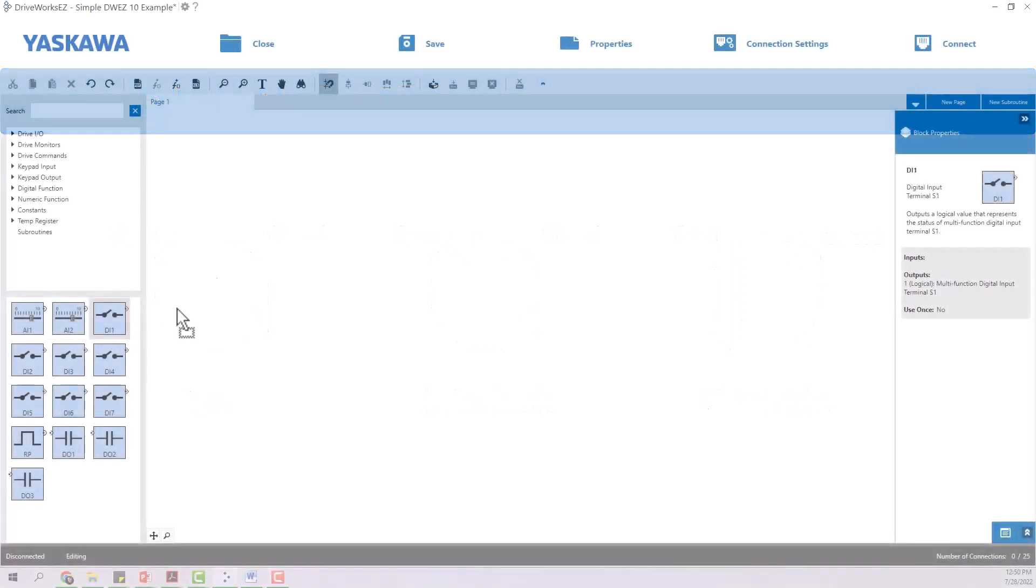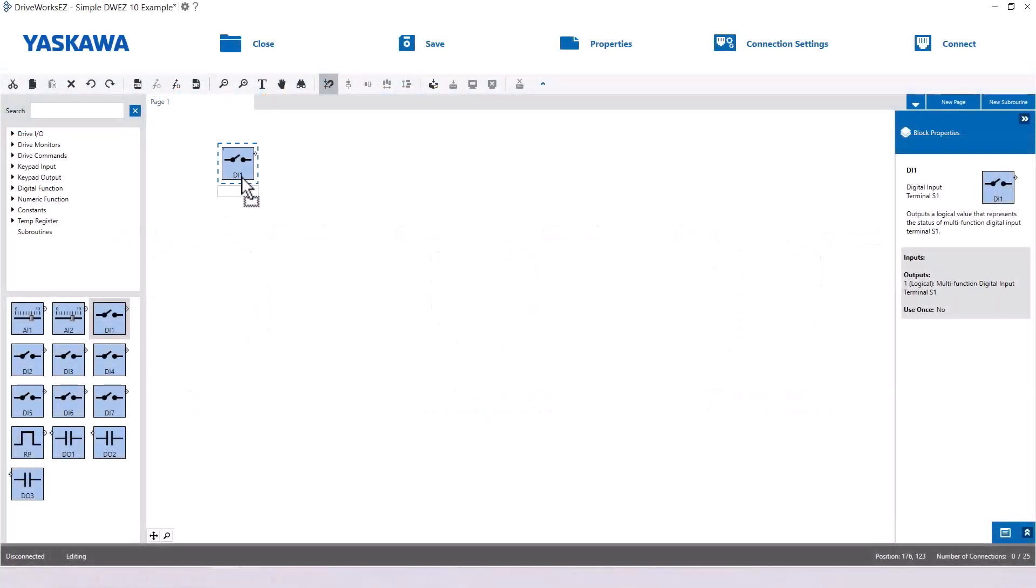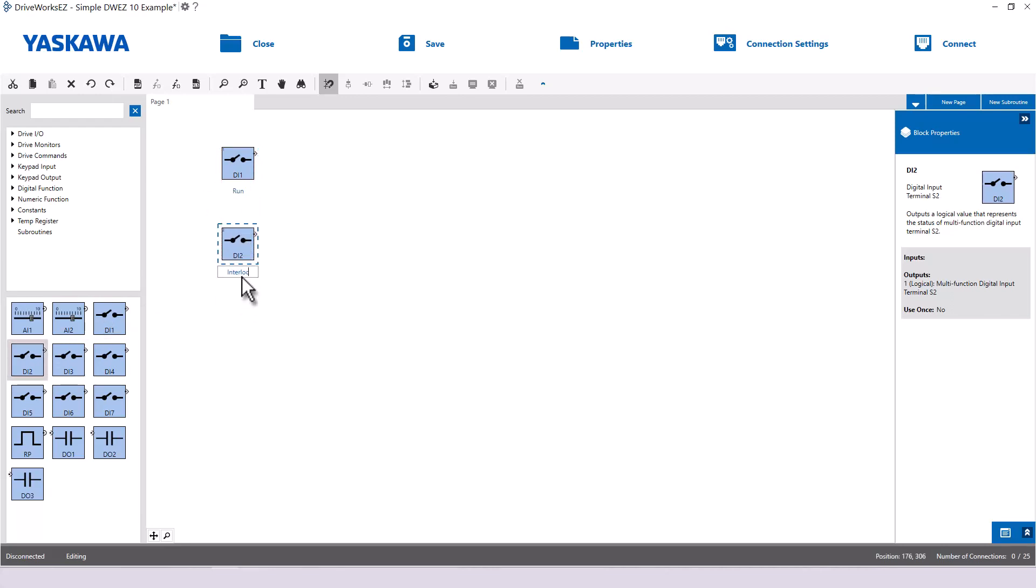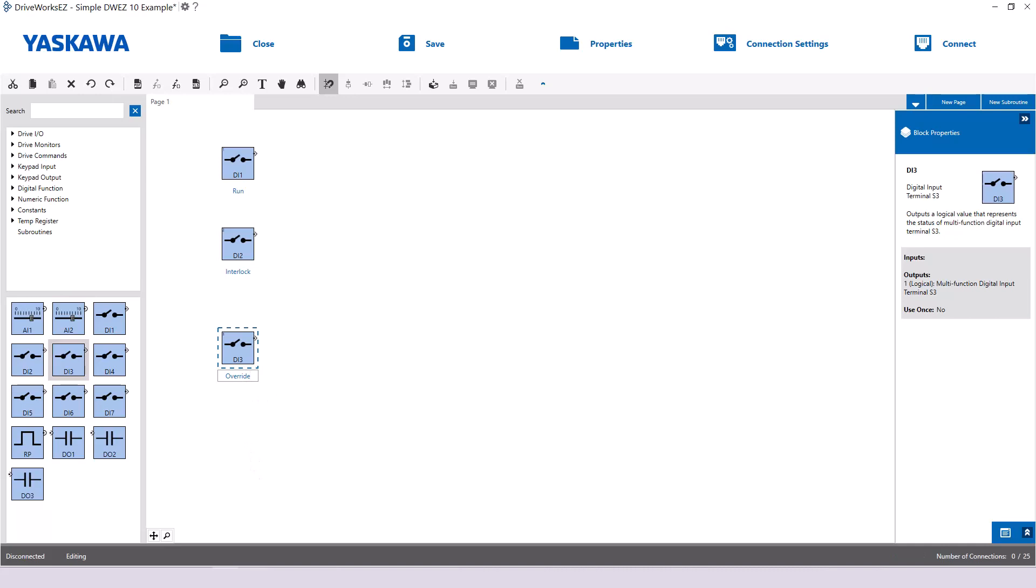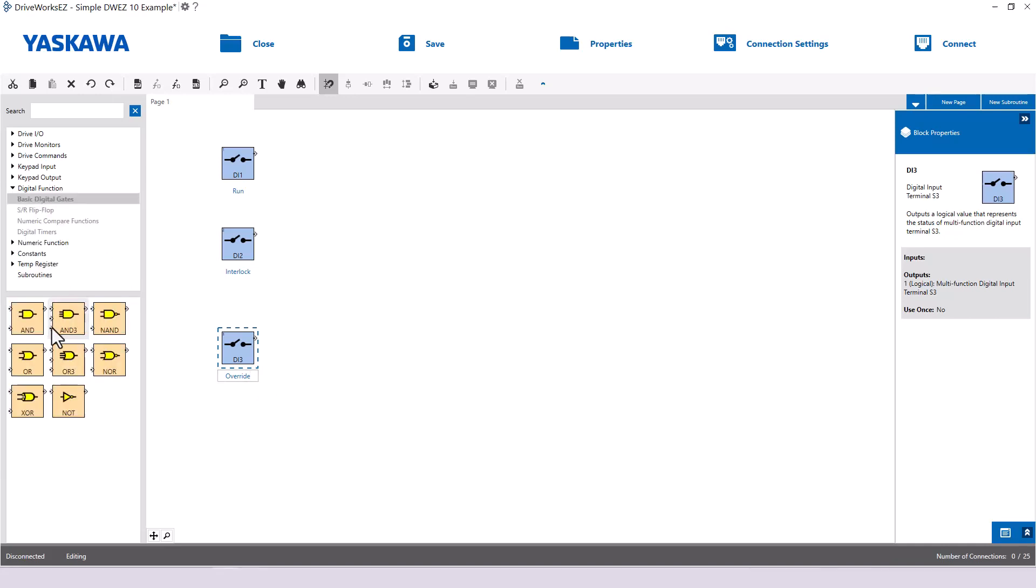For this we can drag three digital inputs onto our blank page. I will name DI1 run, DI2 interlock, and DI3 override so the program is easier to follow. The run and interlock inputs both must be true for the drive to run forward. Therefore, we will use an AND block.